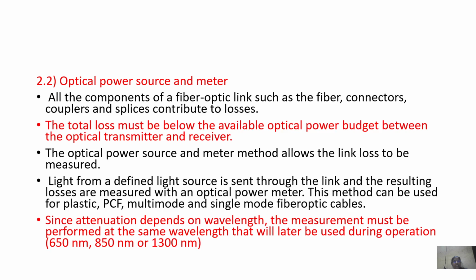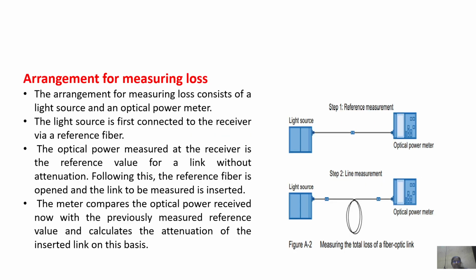Optical power source meter: here, light from a defined light source is sent to the link and the resulting losses are measured with an optical power meter. So here we connect the light source and the optical power meter. A reference optical link is connected, and for that, the loss is measured. Now the actual fiber optic cable is inserted between the reference, and now the loss is measured. From that it is calculated.